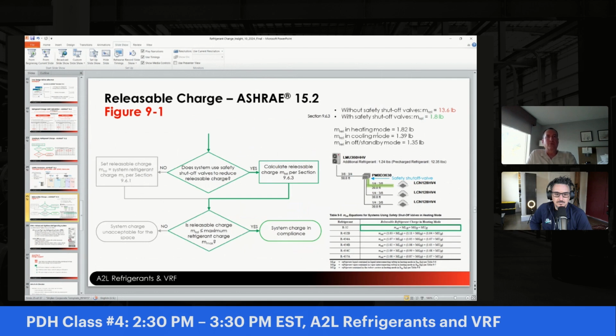There are different levels, whether you're in heating mode, cooling, or off, and you use the highest value in your calculations. So if you utilize safety measures, your releasable charge is compared with the maximum allowable charge instead of the total system charge.